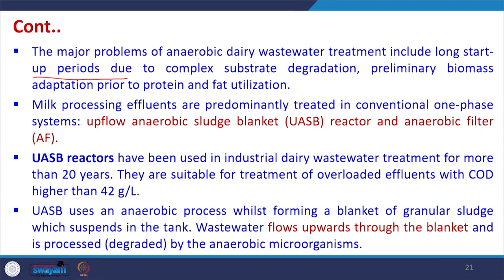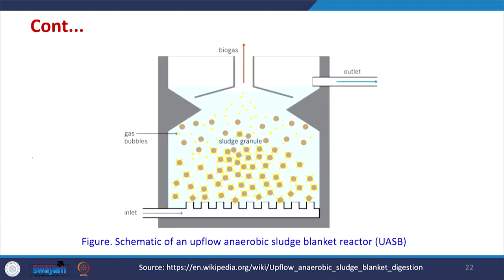Milk processing effluents are predominantly treated in conventional one-phase systems like UASB reactors. We can use upflow anaerobic sludge blanket reactors or anaerobic filter reactors for treatment of dairy wastewater. UASB reactors have been used in dairy wastewater treatment for more than 20 years and are suitable for treatment of overloaded effluents with COD higher than 42 grams per liter. The UASB uses an anaerobic process while forming a blanket of granular sludge which suspends in the cylinder, and wastewater flows upwards through the blanket and is processed by anaerobic microorganisms.